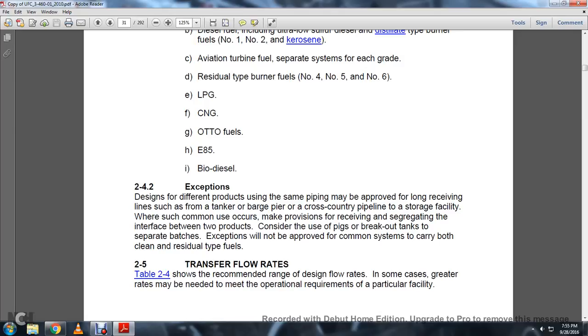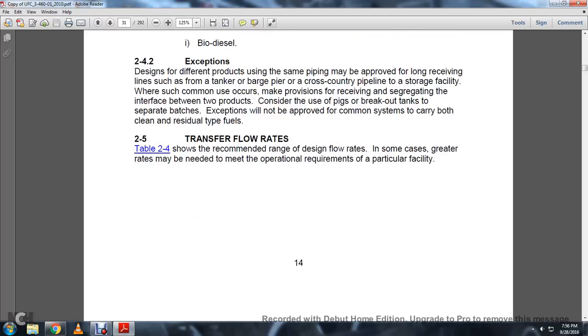E85. And 2-4-2 Exceptions designed for the different product for the same piping may be approved with long receiving lines such as tanker barges, piers, cross-country pipeline storage facilities where some common use occurs but makes provisions for receiving segregation of the interface between the two products. Consider the use of pigs and breakout tanks. Use of pigs or breakout tanks for the separate batches. Exceptions will not be approved for the common systems to carry both clean and residual type fuels.